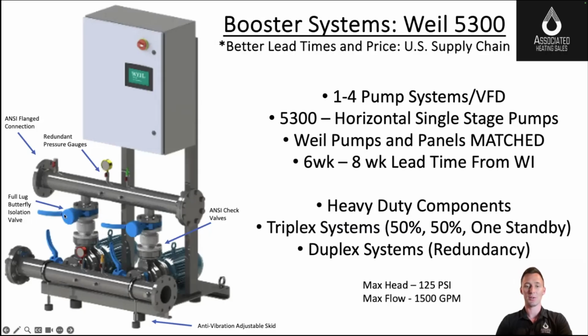And they have full detents here, so you can set these to different settings to provide a little bit more head pressure, and it'll stay in place. It won't work its way over time. The connections are full ANSI connections with end plates. So as you're out on site, you can move discharge and suction to one side versus the other. And then the really nice feature here also is you have redundant pressure gauges on both the suction and the discharge. So you have your digital, which is what your panel's running on, and you have your analog. The nice part about this is if you have a failure of a transducer, which does happen over time, you can quickly look and compare the numbers that you see on the panel to the analog gauge, and you'll be able to understand if that's a quick fix, an easy fix.